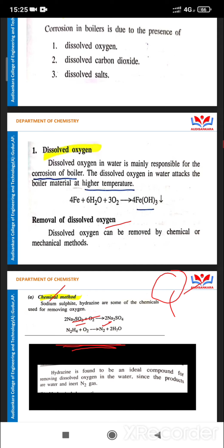How can you remove oxygen? Very simple: two compounds, sodium sulfite and hydrazine, are added. First, sodium sulfite is added to water and the oxygen is completely absorbed, forming 2Na2SO4, sodium sulfate. Next, hydrazine is added to water: N2H4 plus O2 gives rise to N2 plus 2H2O. There is no oxygen left in the water. Hydrazine is an ideal compound for removing dissolved oxygen, since the products are water and inert nitrogen gas.